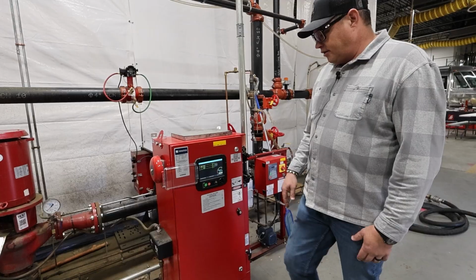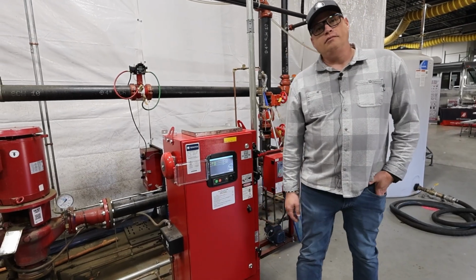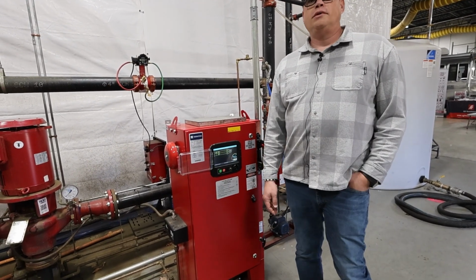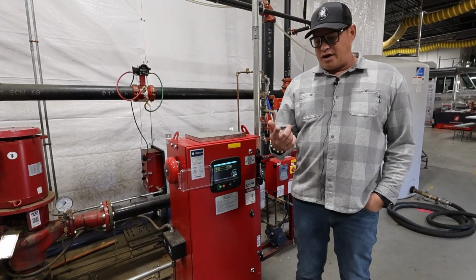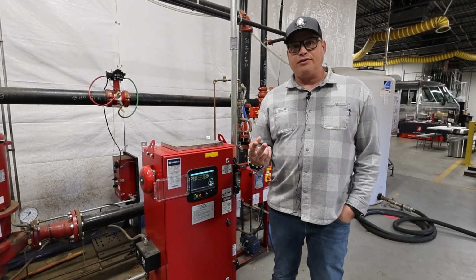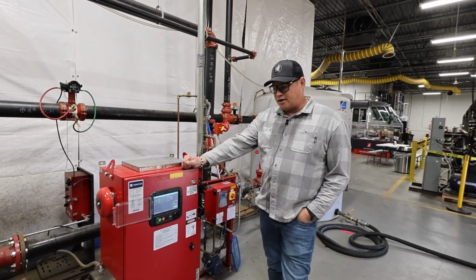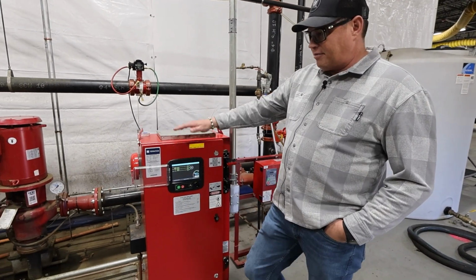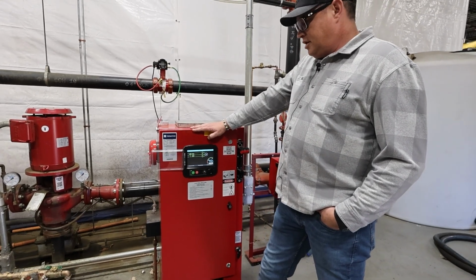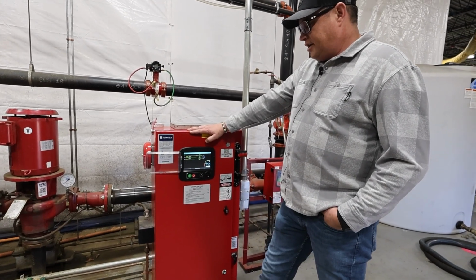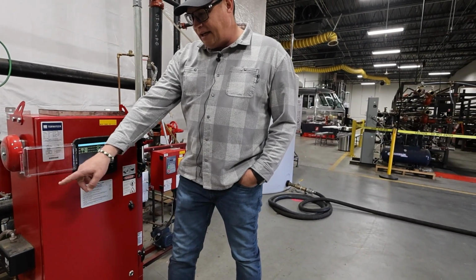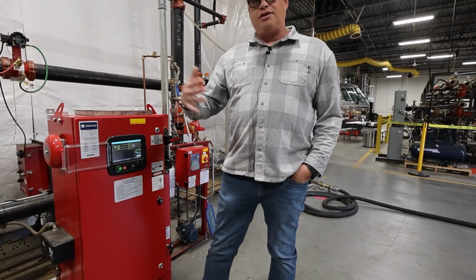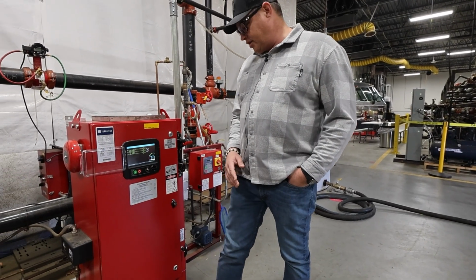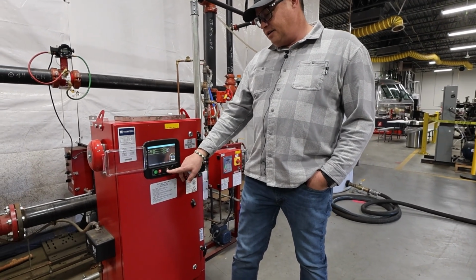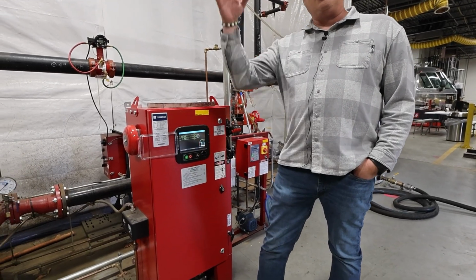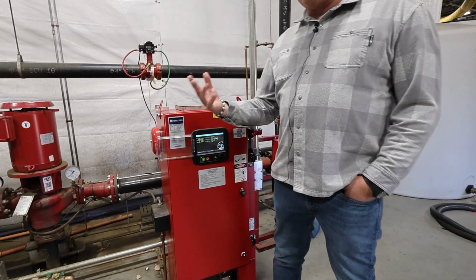Right. So now, you're talking about the things to do in annual, or general startup? Just whether it's general startup or our monthly run tests for electric, or weeklies for our diesels. This time in particular, we're just doing a monthly run test on an electric. So I'm going to hit the start button just to make sure that it starts manually. And then I'm going to also do it using my run test button so that it logs it as a weekly or monthly run test.